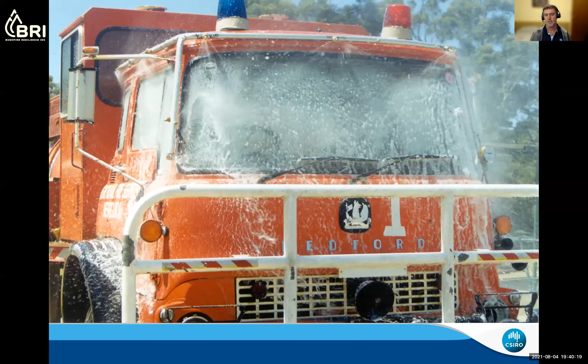The intensity you need to deliver is a constant deluge and constant water film, and only then can you expect things like windows to survive the radiant heat and flame contact they may face. It's quite a specialist system with very high water delivery rates that need to persist for the entire duration of that intensity. Fire trucks are actually specifically designed to survive that very intense peak of fire.